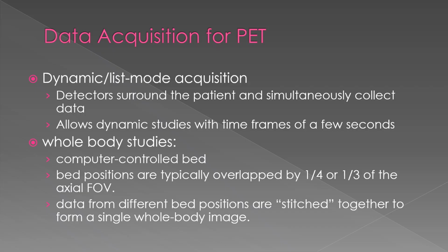actually corrects for it. Sometimes there's an error that you can see where it didn't properly apply those corrections, and you can see the bed positions, but this is an image quality issue that would need corrected with the software. So that's something to keep in mind, but those bed positions do overlap.